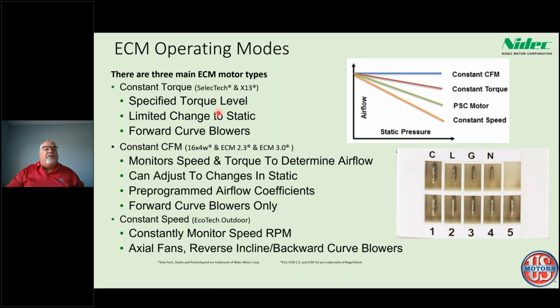The easiest way to identify a constant torque ECM product is to look for the plug. This plug is on the side of all those motors, or all the constant torques, and it has these 5 rectangular plugs on the bottom here. These are your speed taps, or your speed torque values, and the signals come in here, and these are low voltage 24-volt signals. Your high voltage is up here in your L, G, and N area. So that's really a constant torque.